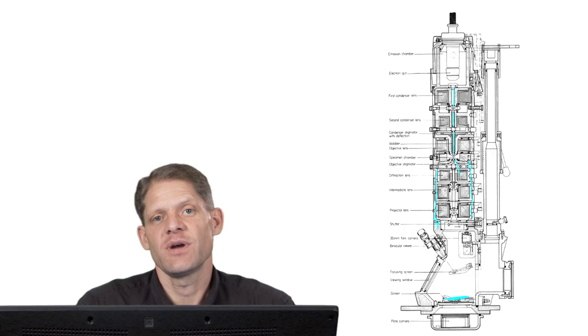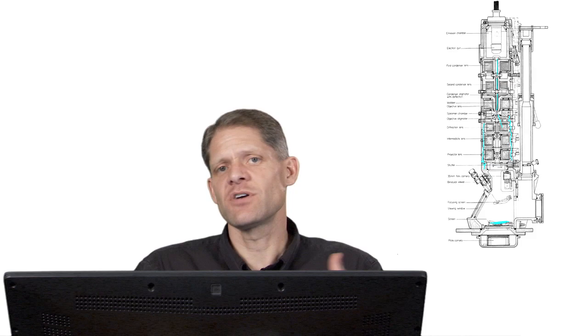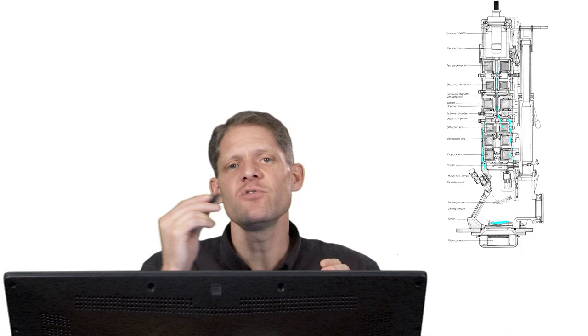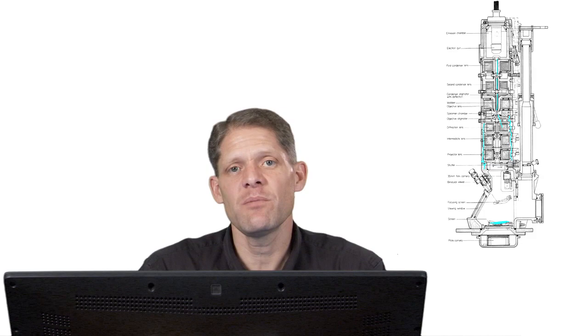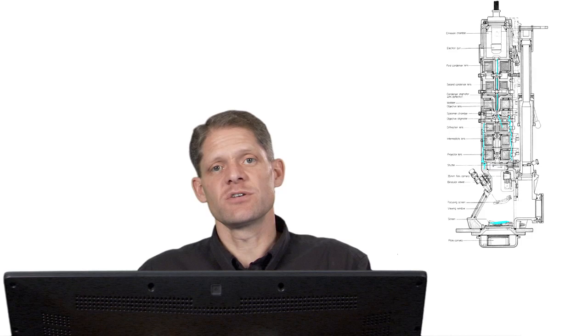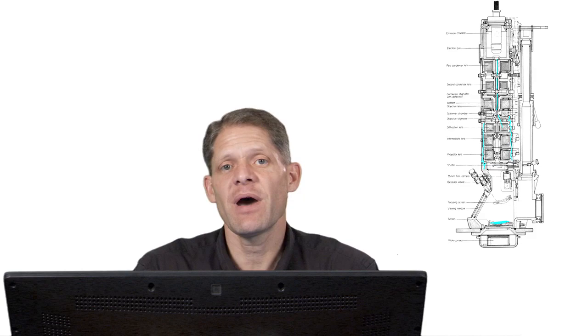Further, you might be surprised to note that within this very complicated electronic machine, there are cooling channels of water pumping through the lenses and all around the microscope to maintain thermal equilibrium. Electron microscopes have associated with them water chillers, and it's very important that the water temperature and the temperature of the lenses remain constant.